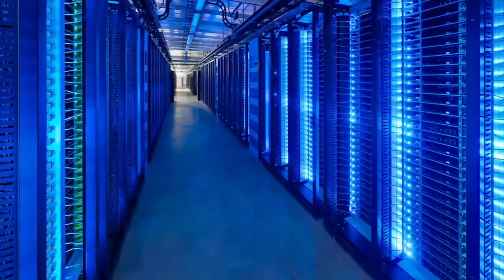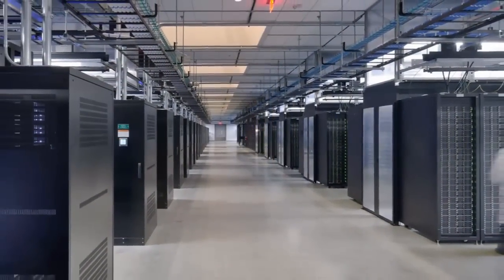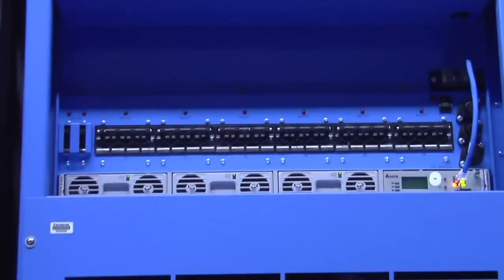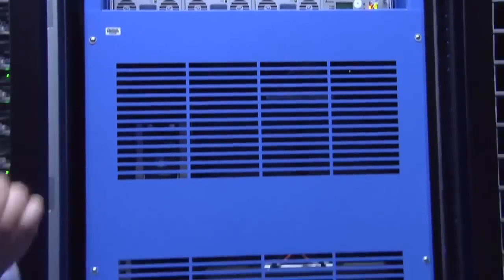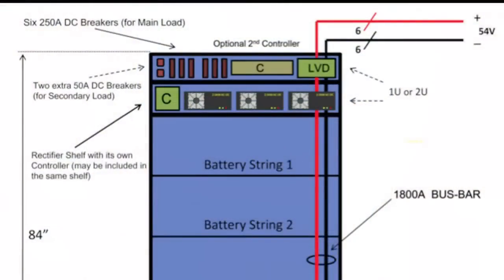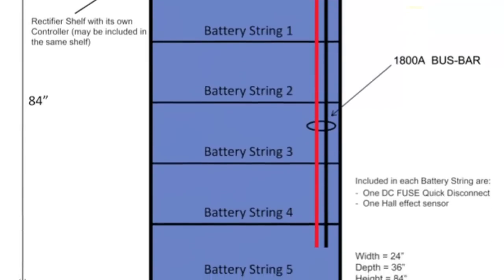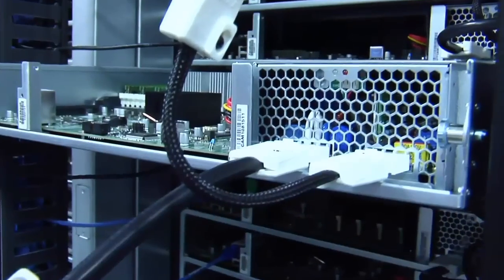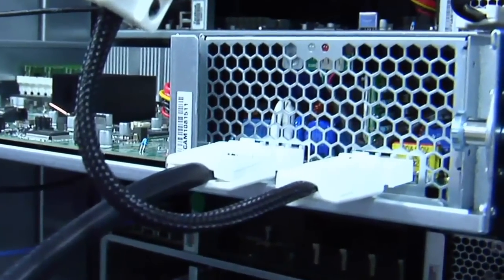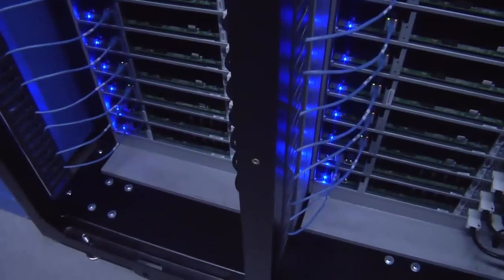This is essentially the Open Compute servers. What you see is what we call a triplet rack, which has 90 servers in it, and another triplet rack on the other side. These two racks are served by this UPS system. We worked with a manufacturer. This is part of the Open Compute project specification that you can download from the website. You can purchase these. I believe it was Delta that worked with us on this one. The servers themselves have a custom power supply with both an AC and a DC connection, which is not terribly typical, so the server can connect both to this UPS or to the AC distribution system.